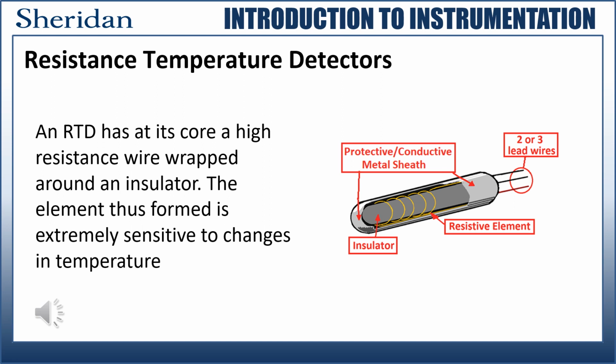But industry and instrumentation need a lot better than crude measurements, so RTDs are highly crafted and laboratory tested for accuracy. The same basic principles of construction apply. A very fine copper wire is coiled around a stable insulator and then covered by a protective heat-conductive metal sheath. They have the end coils lead wires protruding from the end, and it's sealed. Once complete and tested, you have a very precise, directly proportional temperature sensor.